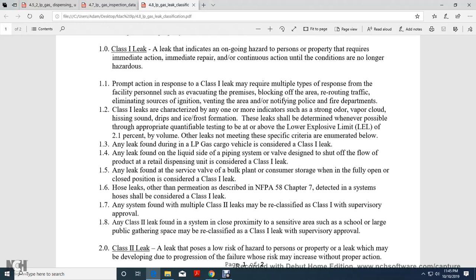Class 1 leaks are categorized by any one or more indicators of a strong odor, vapor cloud, hissing sound, drips, or ice/frost formation. Leaks are determined whenever possible through appropriate qualifying testing to be at or above the Lower Explosive Limit (LEL) of 2.1% by volume. Any leak found during liquid petroleum gas cargo vehicle inspection is considered a Class 1 leak. Any leak found on liquid-side piping system valves designed to shut off the flow of product at a retail dispensing unit is called a Class 1 leak.